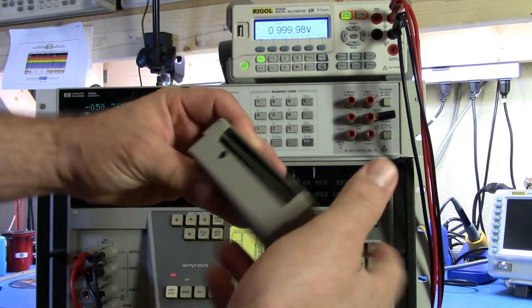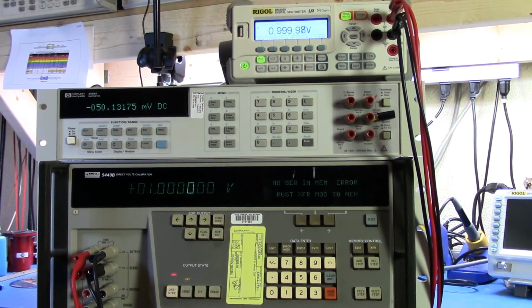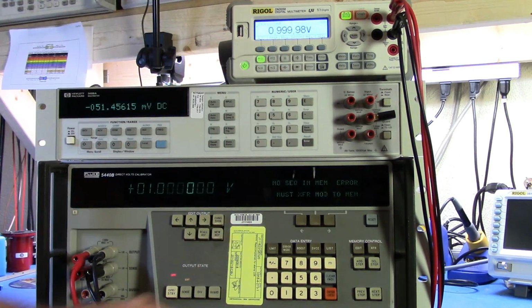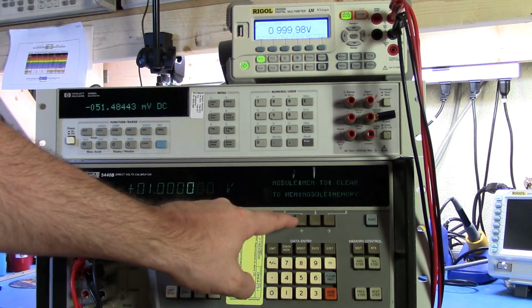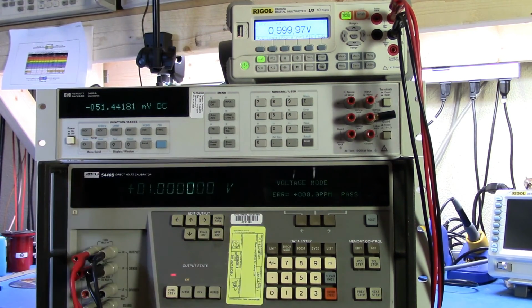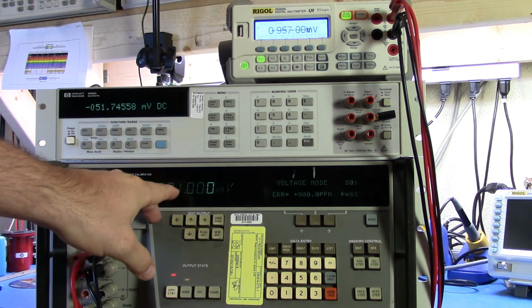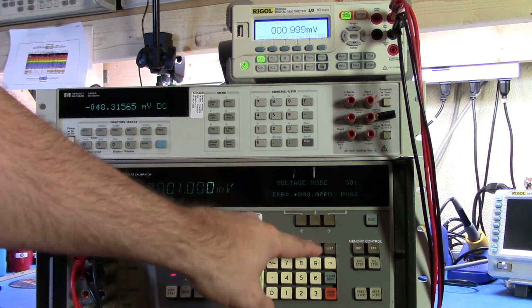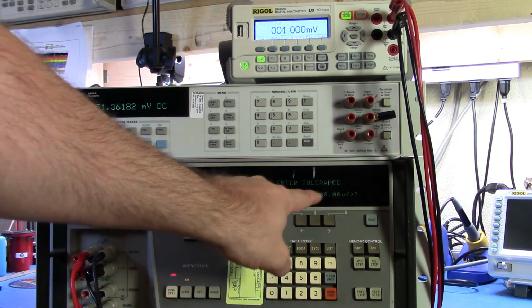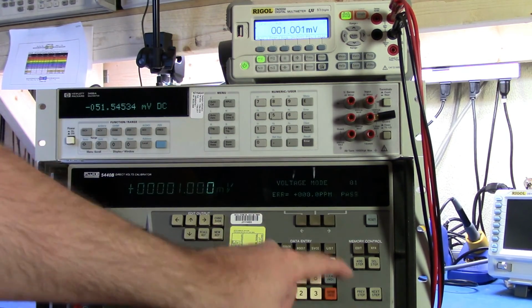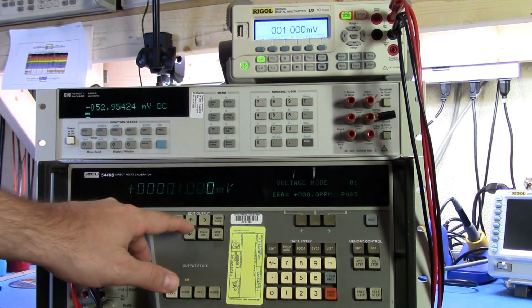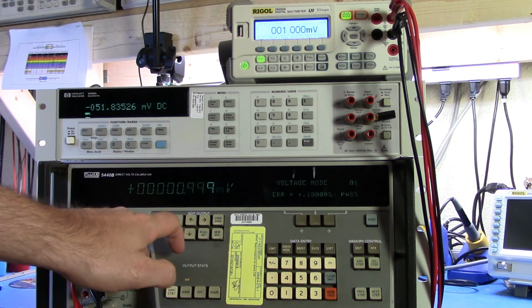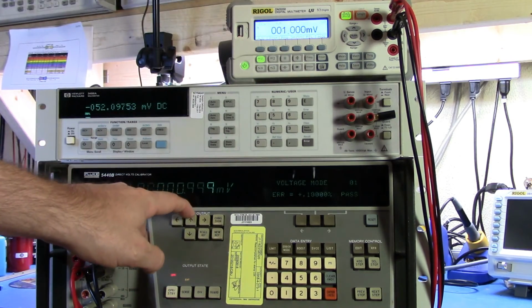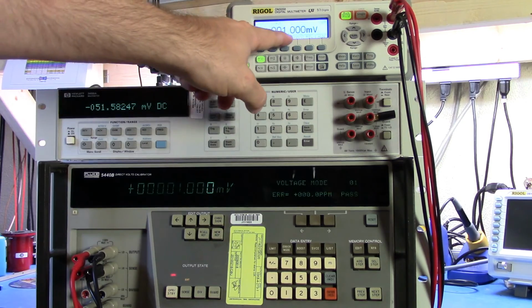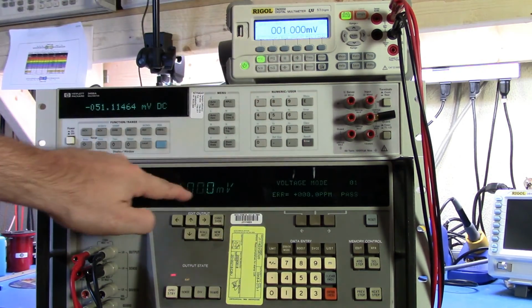What's gone on is this is actually being stored on this little procedure storage module. We had a quick look in here before, but I already have created a set of steps here. So I'm going to go from module to memory, and it's read that in. I'll select step 1, and here you'll see that I'm set for 1 millivolt, and if I have a look at my tolerances, you'll see I've already set the tolerance level here. Now on my 1 millivolt, I can bring that down. We're right at the bottom here, so we're pretty accurate on 1 millivolt.